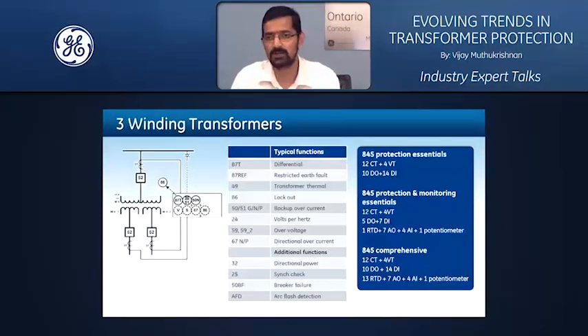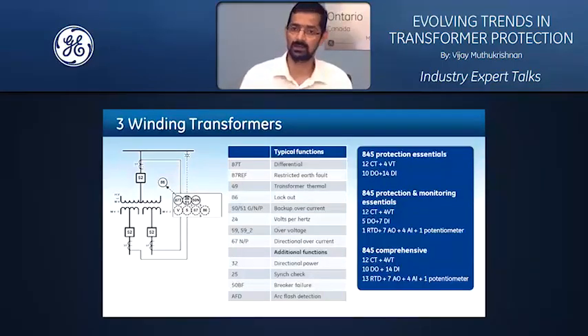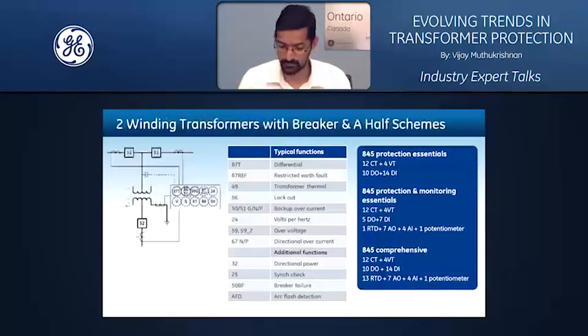In the 845 protection relay, you can easily achieve this by having up to 12 CT inputs as analog subsystems coming in and a 4VT input module combined with either a single or dual combo IO boards that gives you binary inputs and outputs. This can be a base level of protection device for your three-winding applications. In the same way I mentioned, you can expand into a basic level of monitoring or a very comprehensive monitoring and diagnostic functionalities integrated into the 845 itself. That's how you meet your three-winding transformer application requirements.